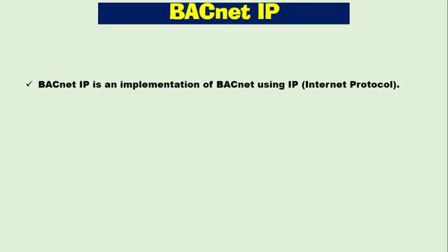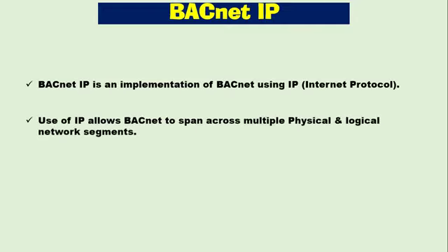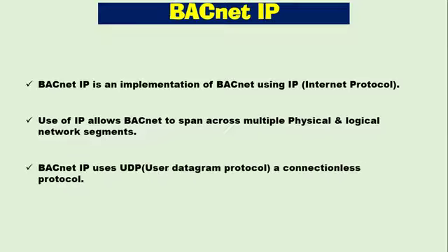BACnet IP is an implementation of the BACnet protocol using IP, which is Internet Protocol. Use of IP allows BACnet to span across multiple physical and logical network segments. BACnet IP uses UDP instead of TCP protocol. UDP stands for User Datagram Protocol, which is a connectionless protocol.